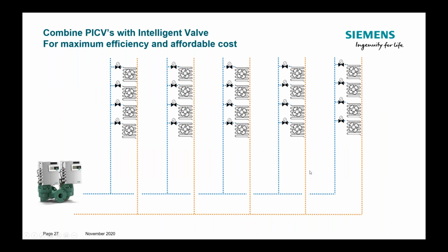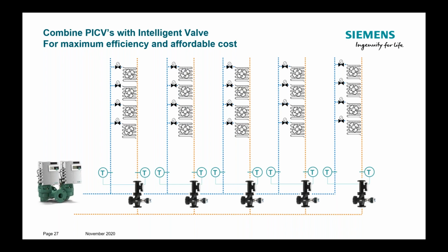Now you might say an intelligent solution like this, with a flow meter and temperature sensors, might be a little bit too expensive for each and any consumer. But think about a solution like here: you have the network with the consumers, and to get to an affordable investment level, you can use PICVs on the consumers and intelligent valve solutions on the risers to have the power distribution under control, and especially to have the DeltaT under control. The PICVs take care of comfort in the rooms and zones, and the intelligent valve solutions take care of efficient operation of the complete network.